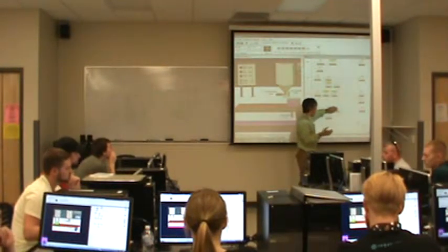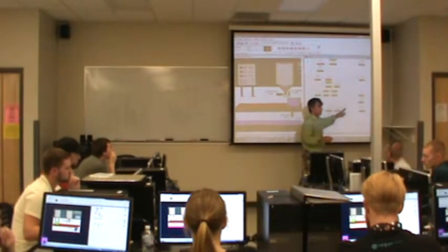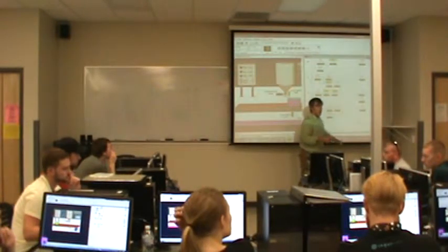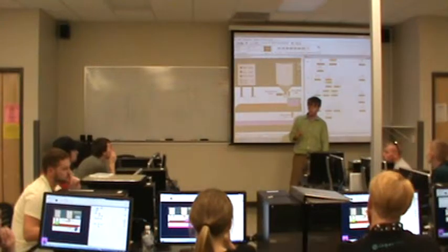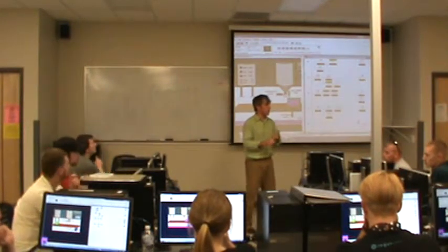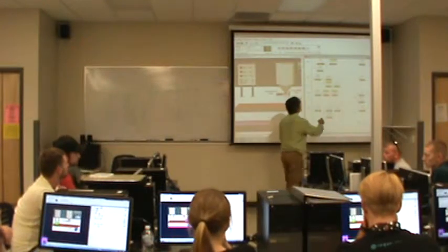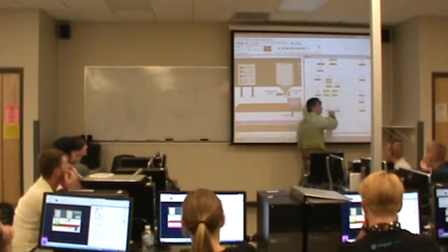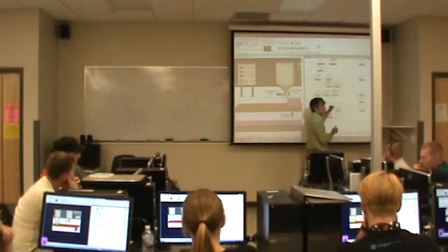And when that happens, we want to OR around it to remember it. Okay? Now, the thing about seal-in circuits is you have to always decide what turns it on and what turns it off. Just like with the start-stop button. What turns on the seal-in circuit is the start button being pressed. What breaks the seal-in is stop being pressed.